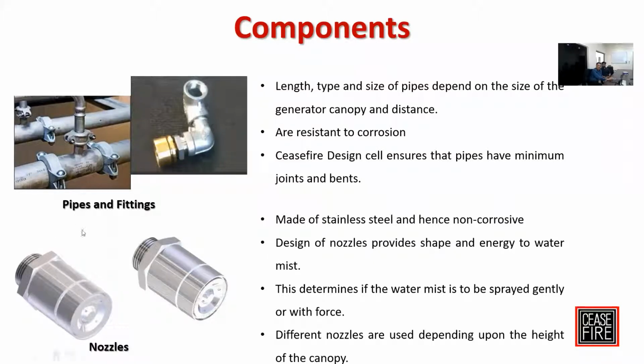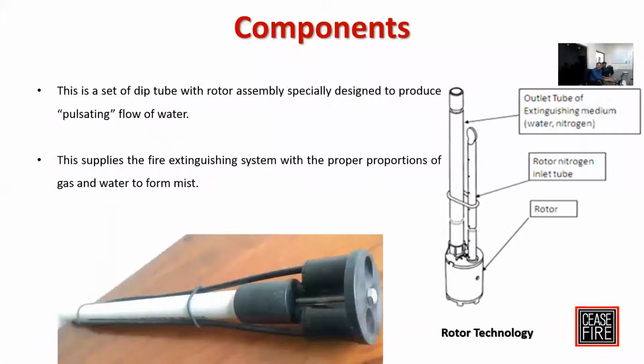You have nozzles. These are specially designed nozzles having two layers of holes inside, one at the center circular and one at the outer side, and they crisscross each other. They are again patented technology nozzles, and they are not any spray or other type. These are specially designed water mist single fluid nozzles, designed for these kinds of applications. These nozzles play a vital role in converting your bubbled water into fine mist particles. Therefore, it is able to quench the fire rapidly. So these are the components.